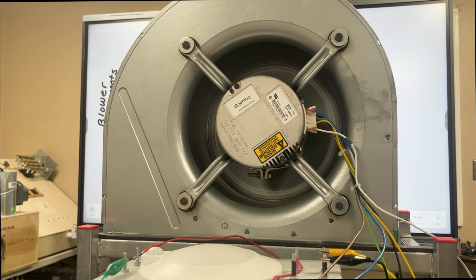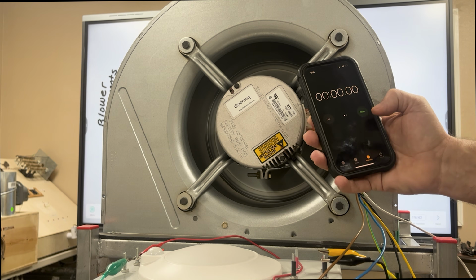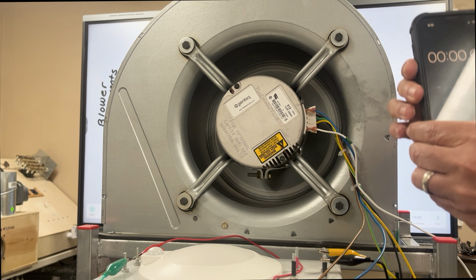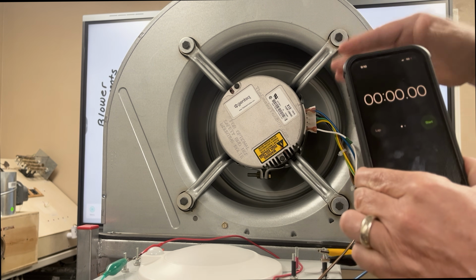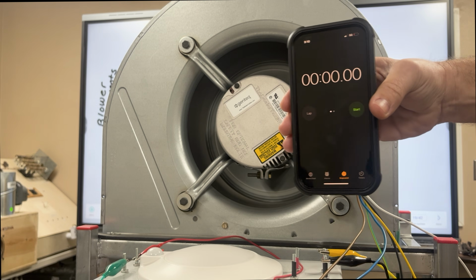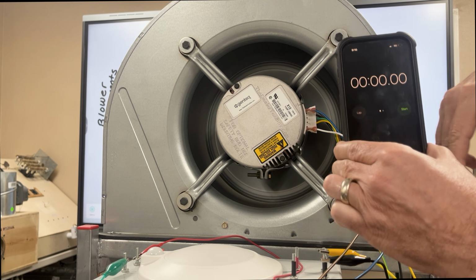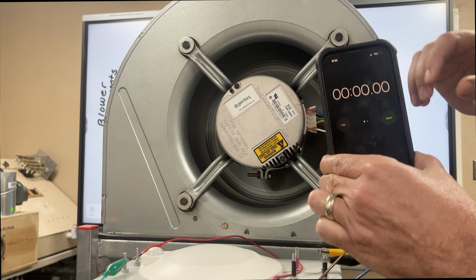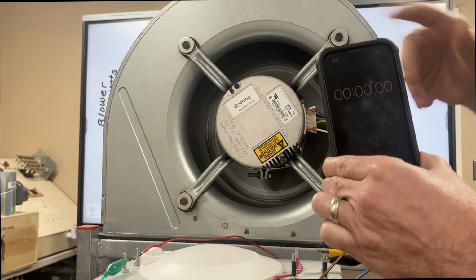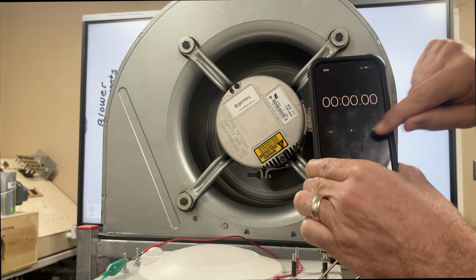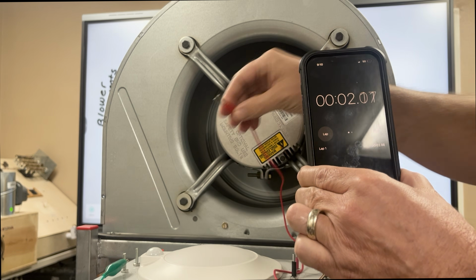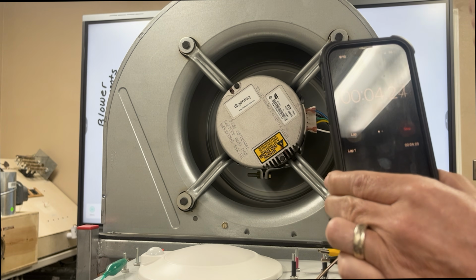So anytime you're diagnosing these, you always want to see what that off delay is. Is my module okay? Does my module have a problem with it? And the only way to know that is to put power on it and get it to run. And then once you remove power, you want to test it on that off cycle. So I'm going to hit start, which I'm a couple seconds ahead of the game. As you can see, I removed power.